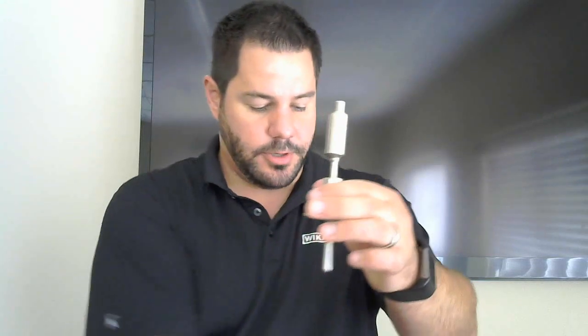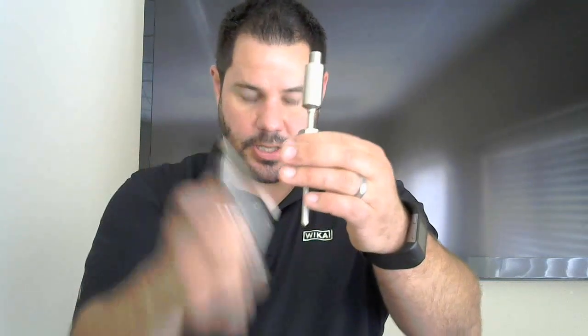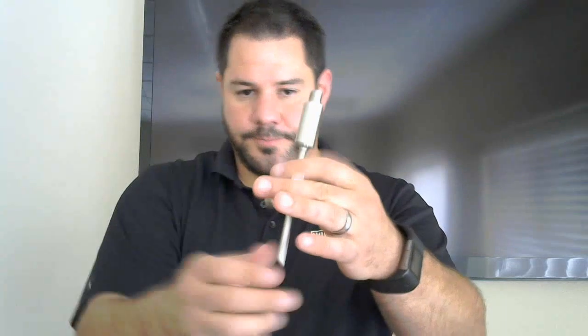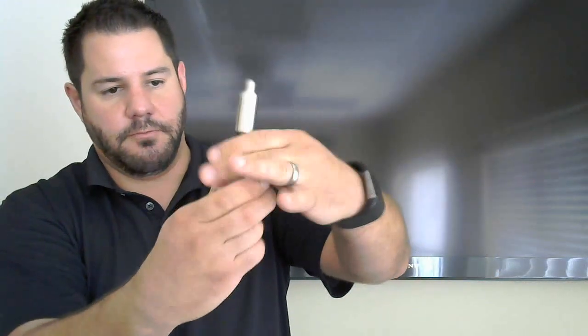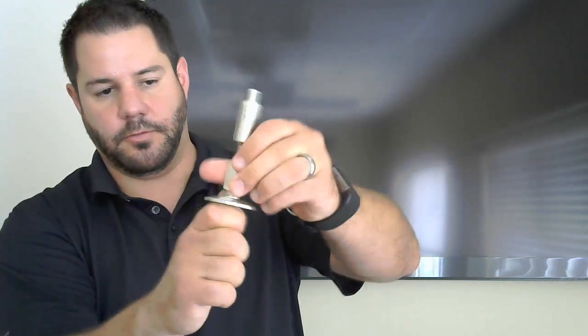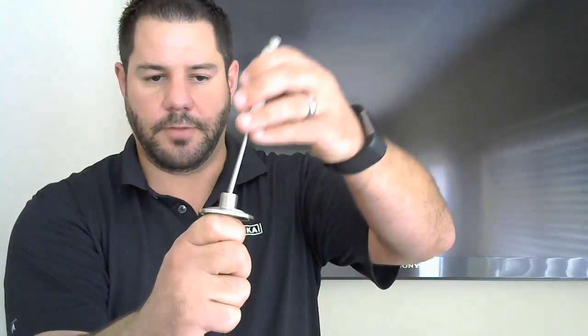So the next design we came up with: we said, why don't we make something where they won't have to open up their system? So we came up with this design, which is a spring-loaded RTD, just like that upper portion, with a 4 to 20 signal. It's removable from the thermo well, which is tri-clamped in. So if you're standing out there, you don't have to open up your process—you just pull the RTD out, calibrate it on the spot, put it back in, and you never opened up your process.